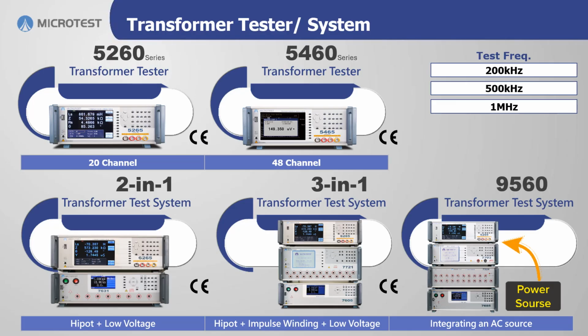Microtest transformer testing instrument is a desktop measurement device that integrates all the electrical parameters needed for transformers into one unit. It primarily measures inductance, leakage inductance, capacitance, DC resistance, AC resistance, and turns ratio. The product line includes the 5260 series with 20 channels, and the 5460 series with 48 channels. Test frequencies are provided at 200 kHz, 500 kHz, and 1 MHz.